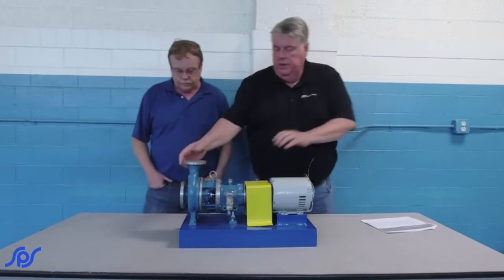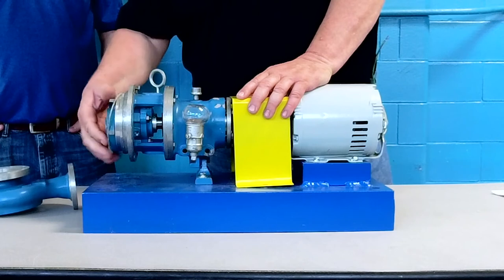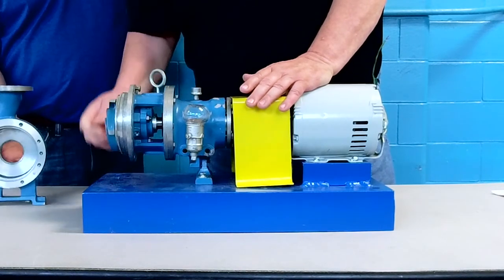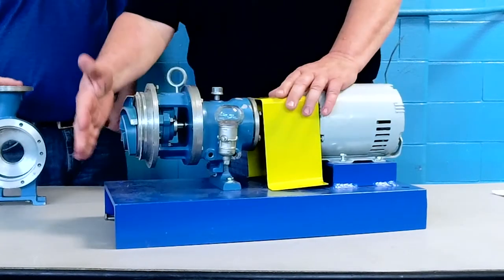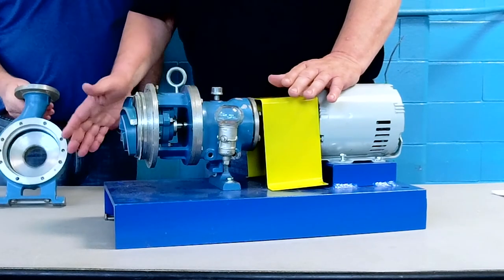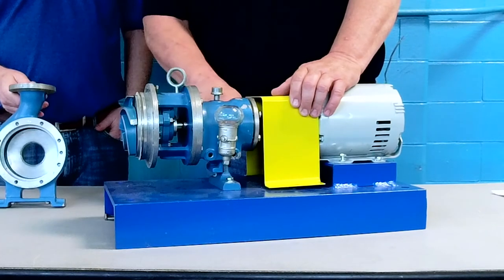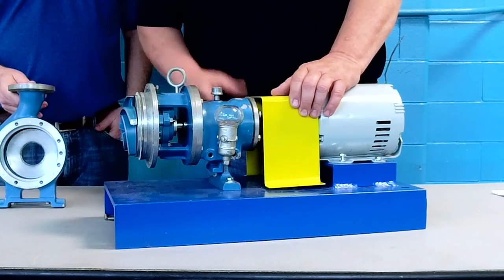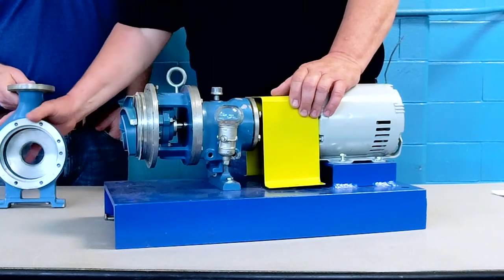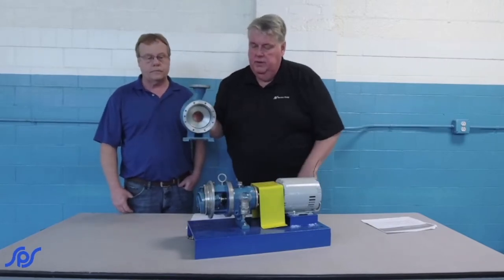As I just showed previously, this particular pump has an open-type impeller with no shroud on it and no wear ring. It has a different kind of adjustment — this one has lockdown bolts and jacking screws on the bearing housing, which enables you to move it in and out to close up the clearance from the impeller to the inside of the volute casing.